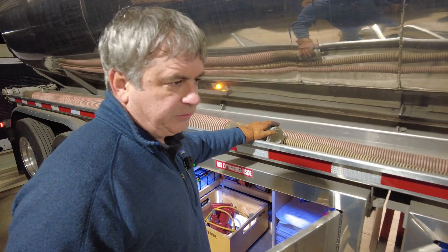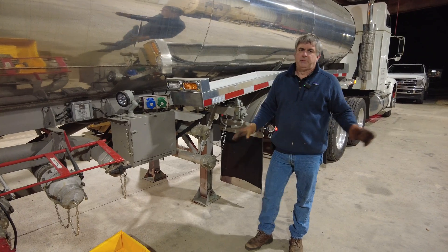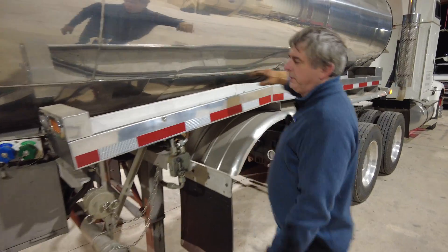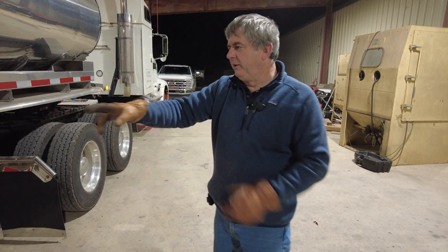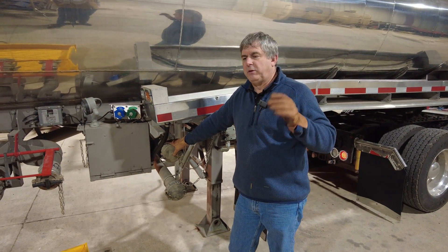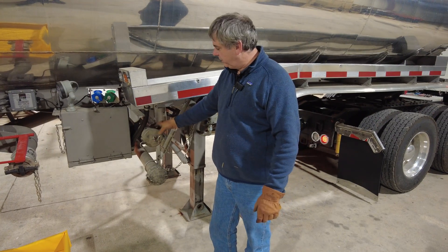The large hoses connect from the load head into a discharge pump. This discharge pump is hooked to a hydraulic pump with hoses that connect to the tractor — it's a wet kit, a hydraulic power takeoff unit off the tractor that powers this big pump underneath. We can do three to four hundred gallons per minute and can pump the whole tanker off if needed — for example, pumping fuel up higher into a different customer tank during a hurricane response.